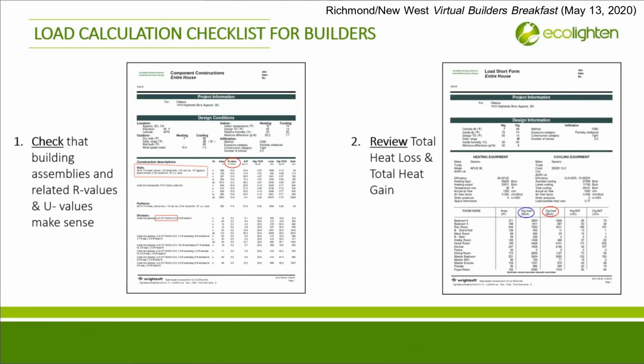If a HOT2000 energy model has been done, check that the loads are within a 10% variance. If the HOT2000 says the peak load condition for the house for heating, for example, is say 50,000 BTUs, then your F280-12 load calculations should be close to 50,000 BTUs within 10%. Review the assembly details to ensure that they're the same on the calculations as they are on the plans, that there wasn't any miscommunication. And make sure the design conditions, such as the outdoor and indoor winter and summer temperatures, are reasonable for your location and are in the correct climate zone.